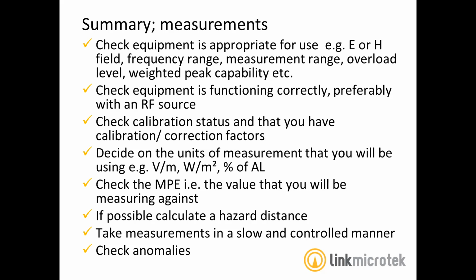And make sure that you understand what the action level or the limit is that you are measuring against. So be clear that, particularly where you're not measuring in terms of percentage of standards, but reading in terms of volts per meter or Tesla, what limit am I measuring against? Because when you get close to the limit, you'll be wanting to make more measurements. If possible, beforehand, calculate hazard distance if you can. Take measurements in a slow and controlled manner. And if you get any anomalies or things that don't quite seem right, then just recheck anything that doesn't seem right.